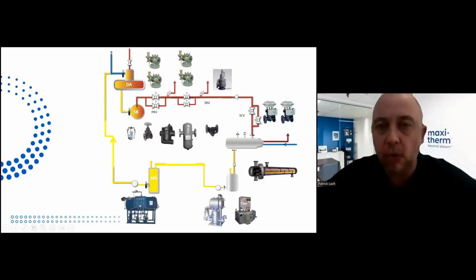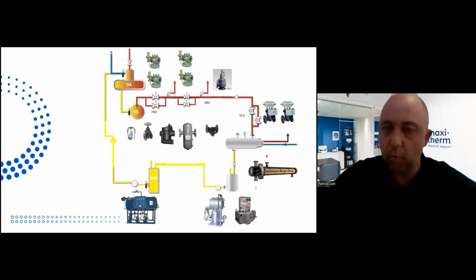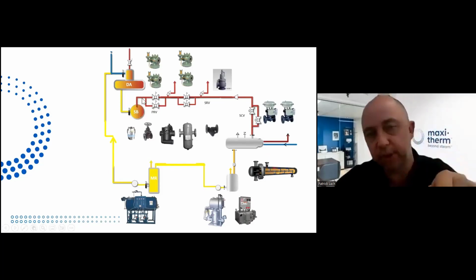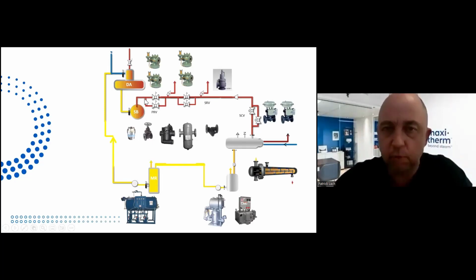So this is a typical conventional design for a heat exchanger, right? So you're coming out of the steam boiler somewhere, pulling out high pressure steam, coming in every mechanical room or building on the campus or in the city. You need a PRV station. Some of you will go with a 1/3, 2/3, and also 2-stage, let's say 150 to 60 and 60 to 10 for better reliability or control. You need steam safety relief valves, vent to the roof, bigger pipe, low pressure steam volume is much bigger, so more welding, more firewatch, more installation.